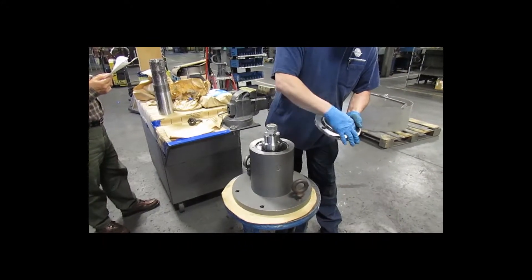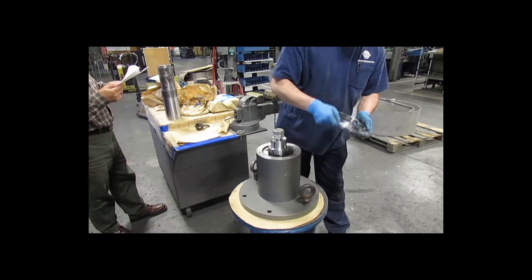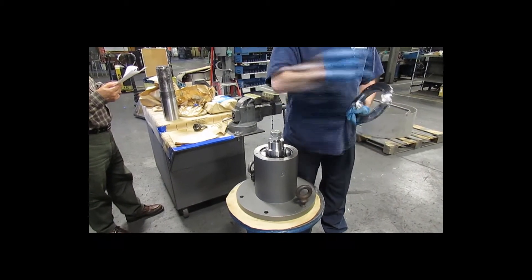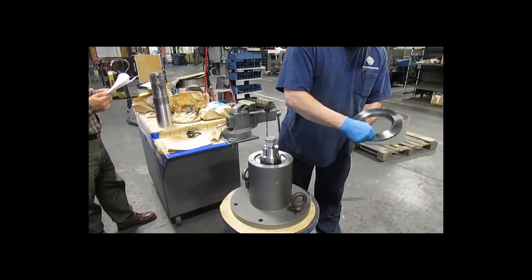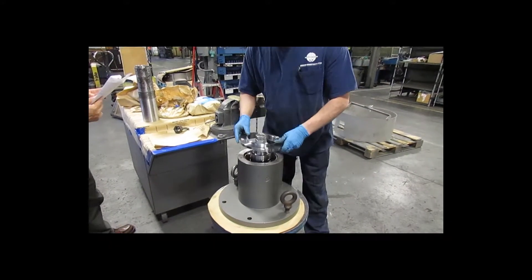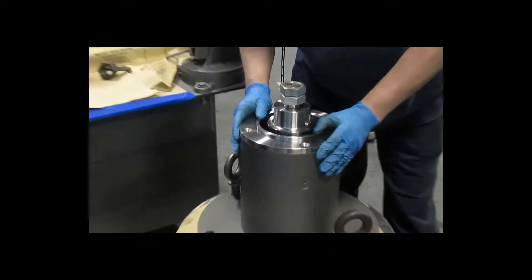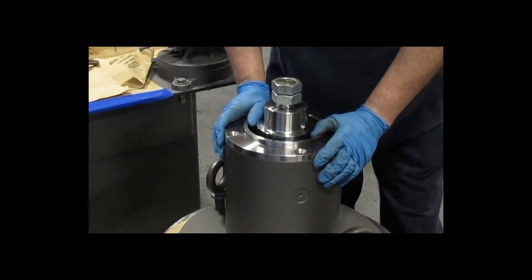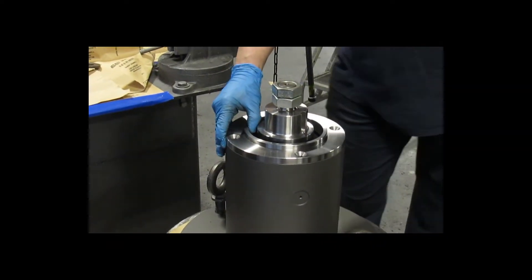The upper rotor end cover would be the next part to be installed. It has four holes that are countersunk on one side. It can only be installed in one manner. There's a shoulder on the inside which seats against the outer race of the upper rotor bearing.